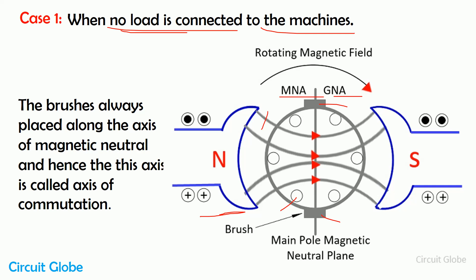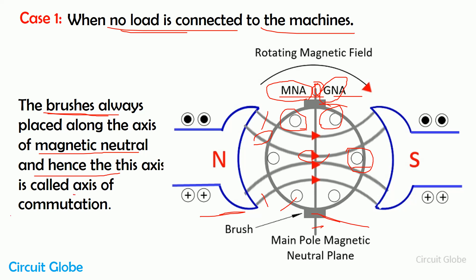No load is connected to the machine means no current flows through the armature conductor, which means no flux is induced in the armature conductor. So only the main field flux is present in the DC generator, and that flux is symmetrically distributed between the armature conductors. This is the polar axis — the central line between the north and south pole. Brushes are always placed along the magnetic neutral axis, and here the magnetic neutral axis and the geometrical neutral axis coincide. This axis is also called the axis of commutation.